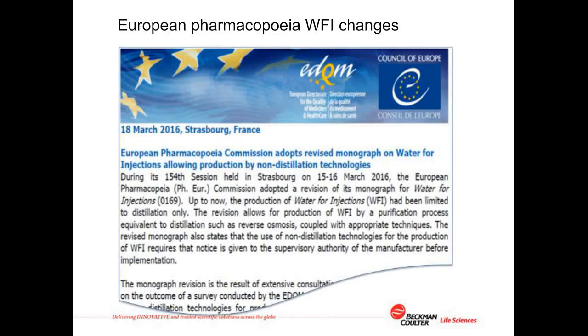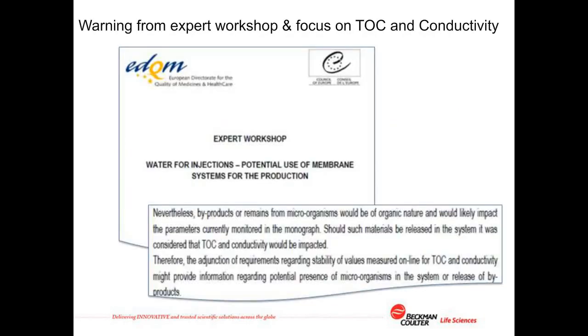Online monitoring, particularly for TOC and conductivity, has taken on an even greater significance since the European Pharmacopoeia adopted its revised monograph on water for injection in March of 2016, allowing for the first time the generation of water for injection from reverse osmosis. The working group responsible for advising the European Directorate on their new water for injection monograph gave a warning that reverse osmosis may not be as robust as stills, and they encouraged a focus on online TOC and conductivity monitoring as early warning of potential RO integrity breaches.